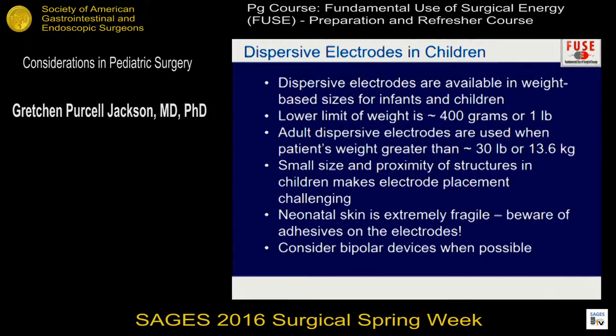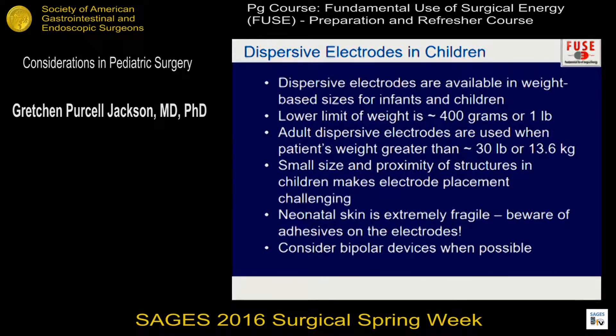Regarding dispersive electrodes — we don't use the same large Bovie pad used in adults. They are available in weight-based sizes for infants and children. The lower limit is about 400 grams, or about one pound. Adult-size electrodes can be used when the patient's weight exceeds about 30 pounds, or 13.5 kilograms.